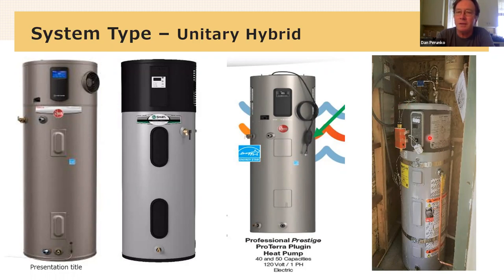Personally, I don't think that this is the right strategy for a confined space. I think you're better off venting the space, but also ducting the unit to outside. Because in this particular install, the thing is releasing cold air into the space that it's in, and there's nothing driving that cold air out of the space to outside. And so what you want is to get the cold air from the unit all the way out of the space and new air from outside around the machine. So it has access to new air.